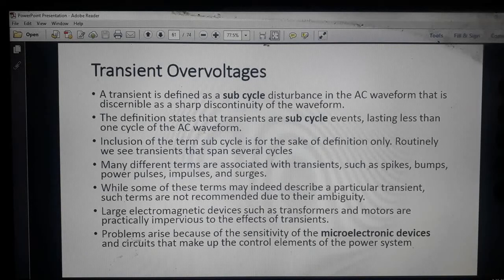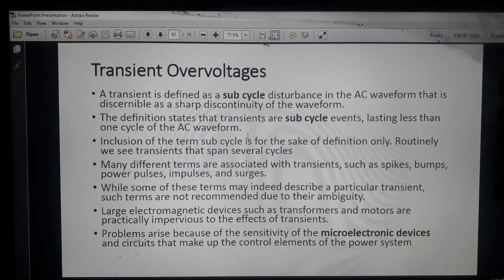The definition states that a transient is a sub-cycle event. Sub-cycle event means that if we are talking about the transient over voltage, it may be some part of the complete cycle, known as sub-cycle, lasting less than one cycle of the AC waveform, maybe less than one complete cycle. Changes will occur in less than one cycle of the AC waveform. That is known as transient over voltage.